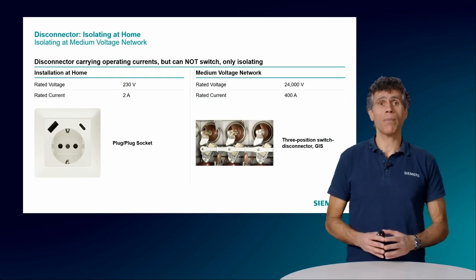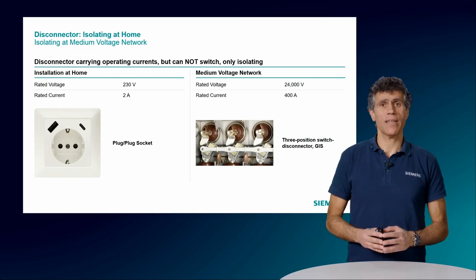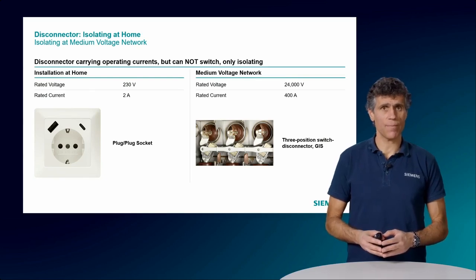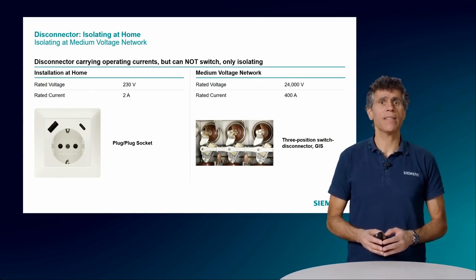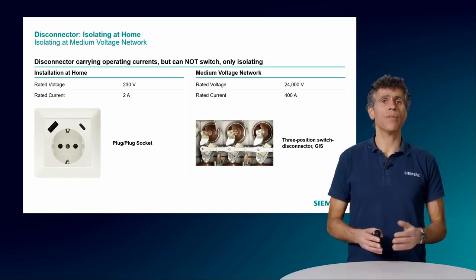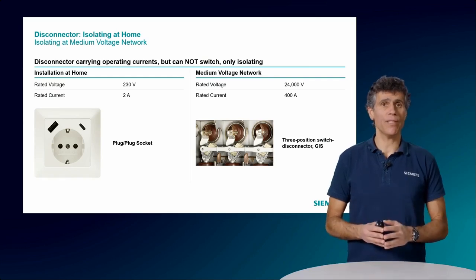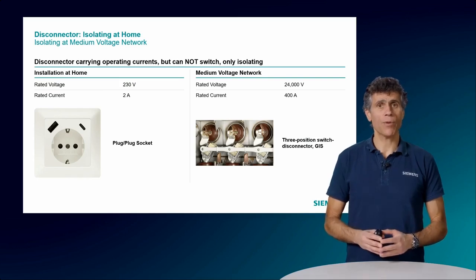I bet you never saw your plug as a device as such, but it is, and it's in fact a very important one. The differences for the medium voltage are, of course, the higher voltage that it can withstand and the higher safety features, such as lockout capabilities to prevent accidental re-energization. So basically, this device fulfills two tasks. It creates a safe isolation and it provides a visible break, allowing the operator to confirm visually that the circuit is de-energized. This is very often required by standards and regulations for safety purposes.